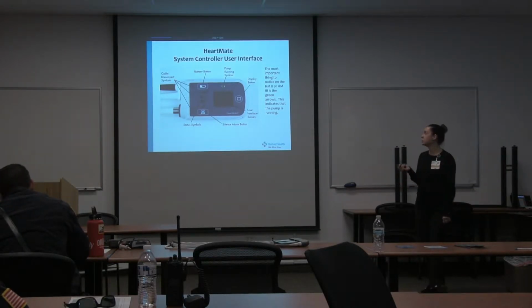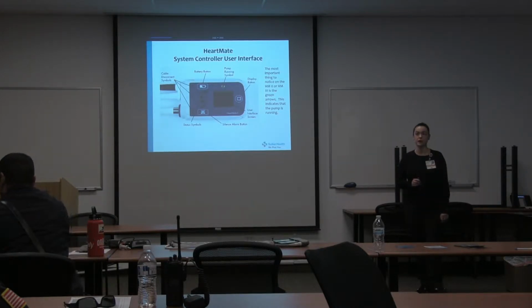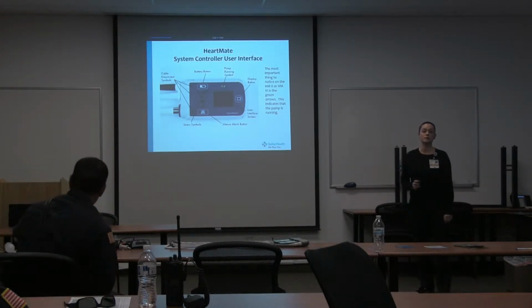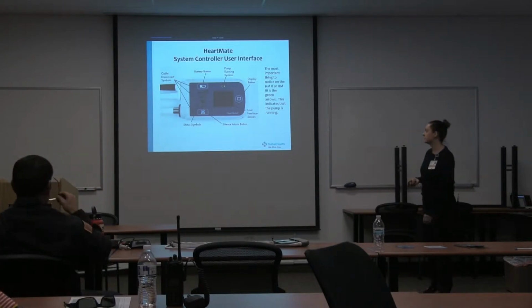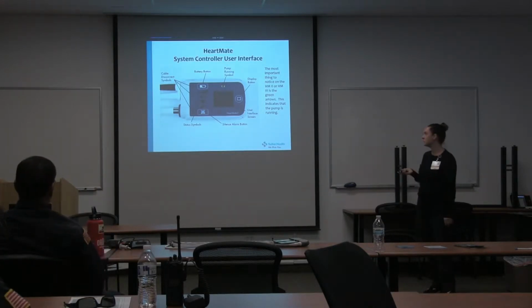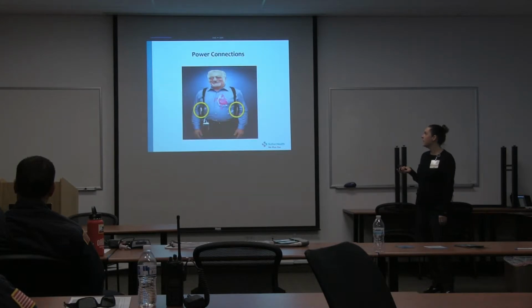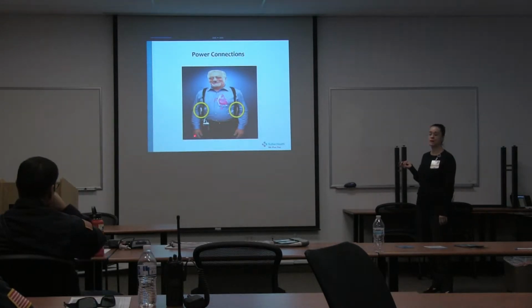The Abbott Corporation, one of my favorite things is they have this green light on the front of their controller. So no matter what alarm is going off on this controller, if the green lights are on, you know for a fact that the patient's pump is pumping inside their body. So always think green is good, green is go. If you see a green light, you can take a deep breath and know that the pump inside the patient's body is pumping. The power connections look like this when the patient's up and mobile.